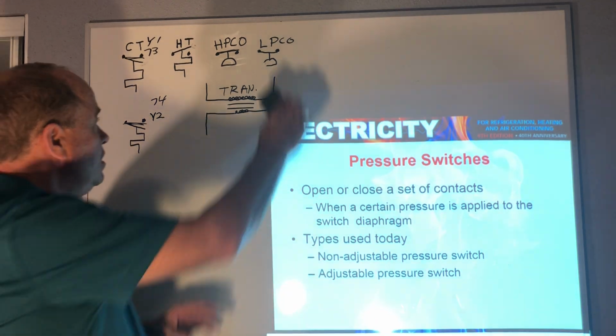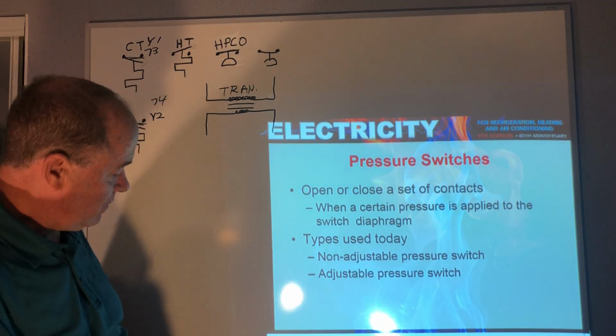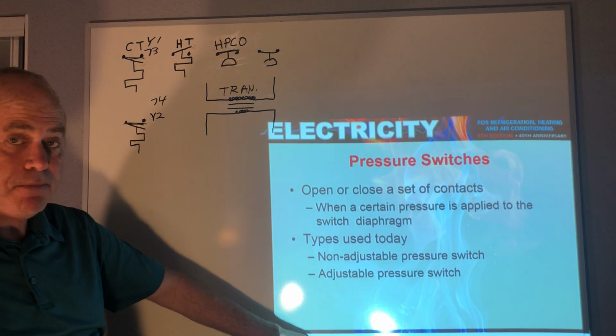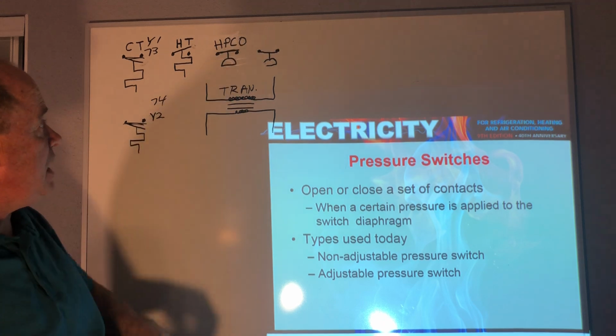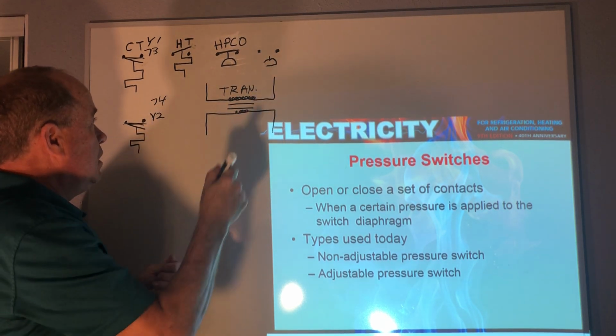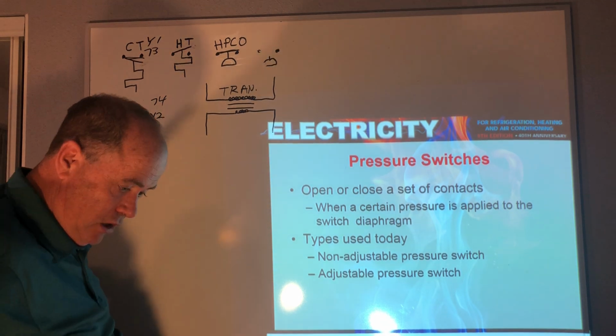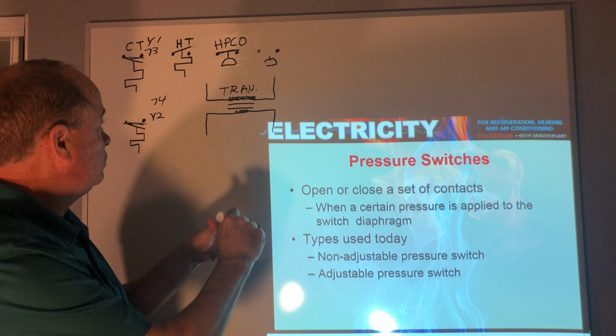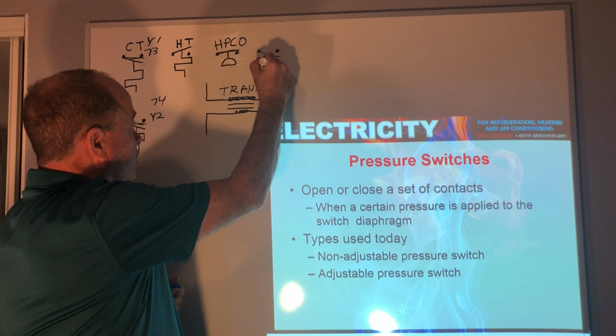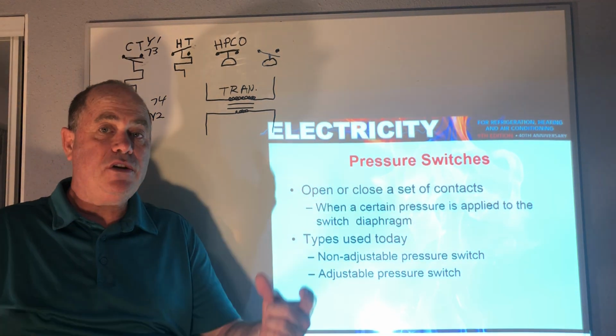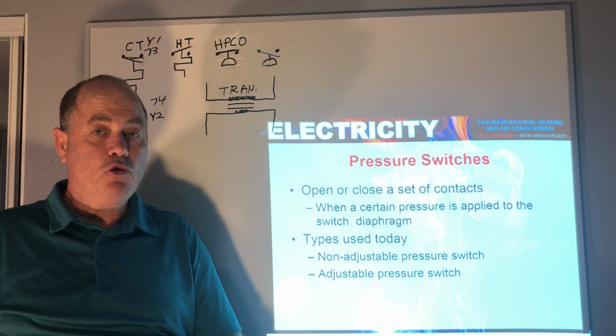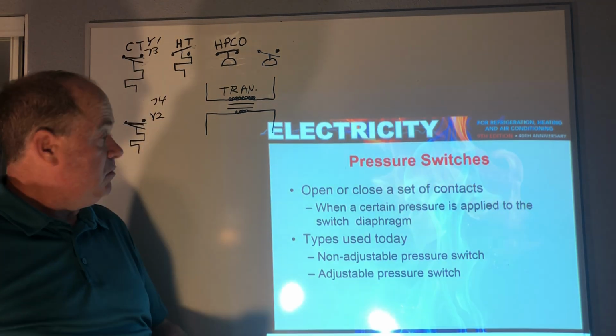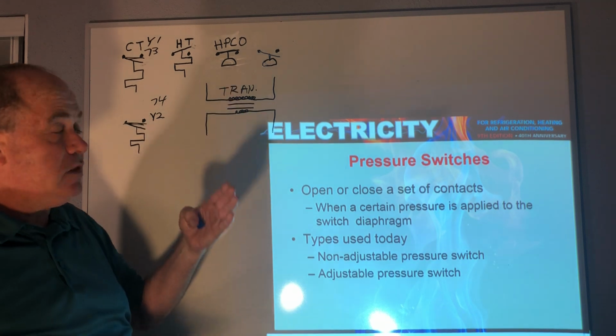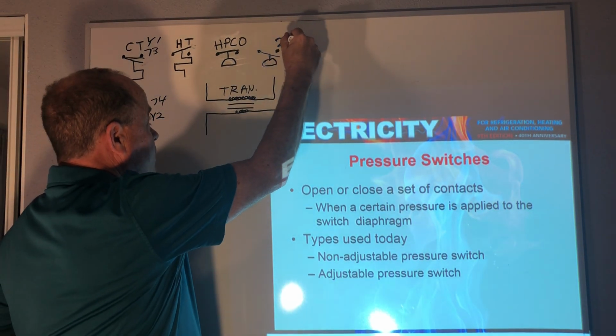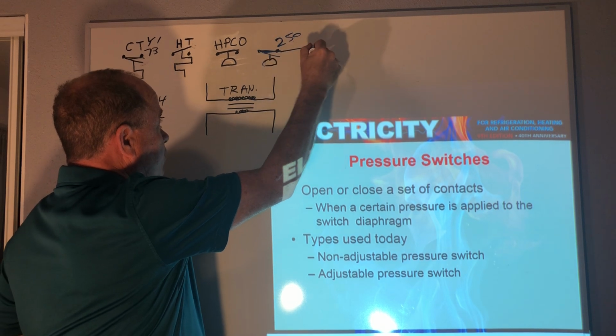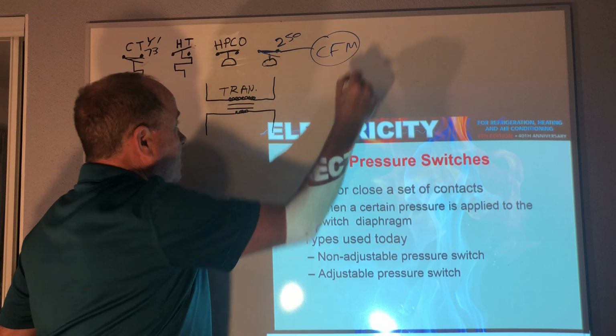On larger systems, we can also have a pressure switch that makes on a pressure rise, like this one, and might be drawn normally open. Let's say you start with one compressor and one condenser fan running when you bring on the cooling. But then if the head pressure rises, let's say to 250 because it's a warm day, that closes and brings on a second condenser fan motor.